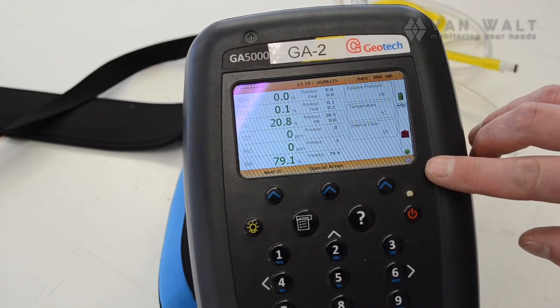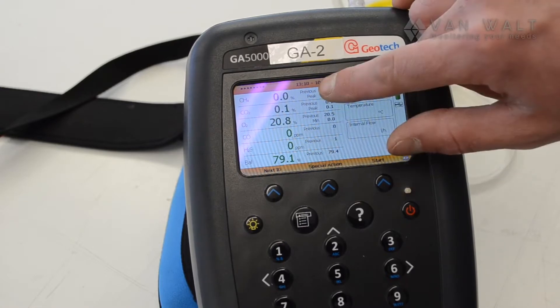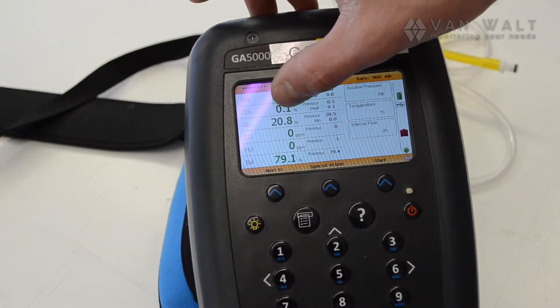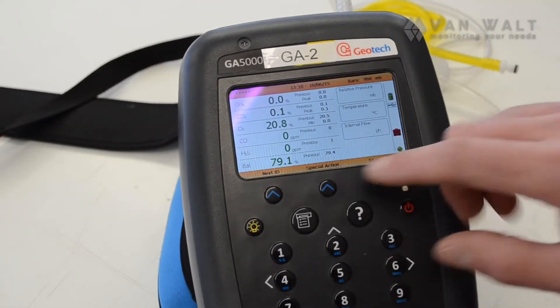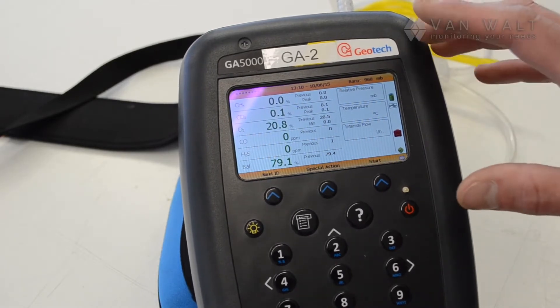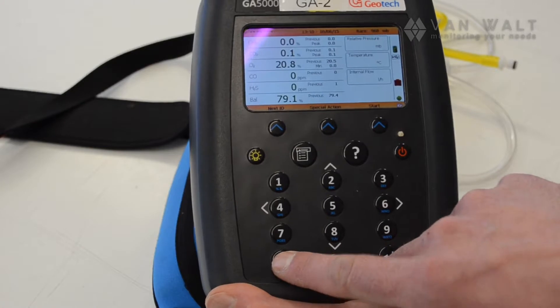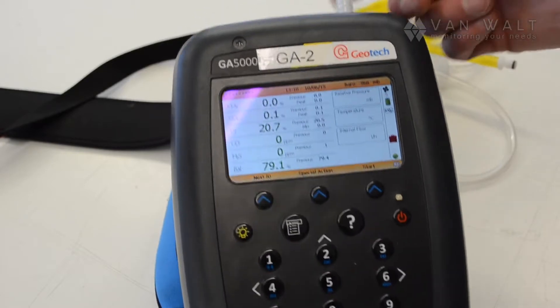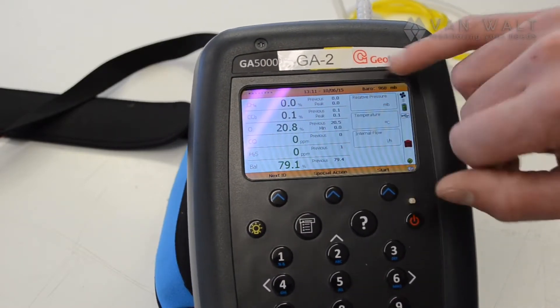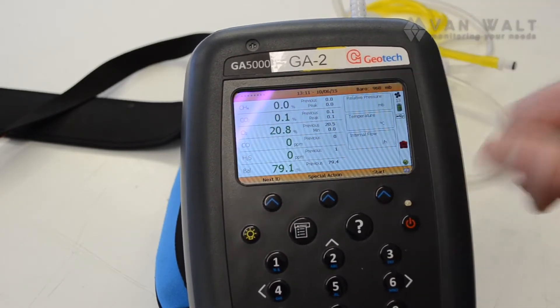Immediately we're in the run screen with live readings for our parameters: methane, carbon dioxide, oxygen, carbon monoxide, hydrogen sulfide, and the balance. The pump needs to be operating to sample from the sample tube — that's done with this fan button at the bottom left. Click it and we're now pumping through the sample tube, getting live readings. Peak readings are held on the second menu.